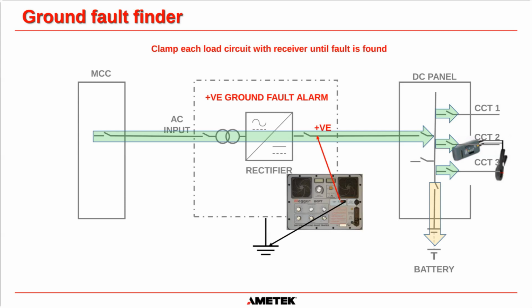I make it sound very easy using this equipment. I've used the system in the UK a lot, not this Mega one, but the one that I used to work. It does take practice. You do have to tune it. You have to read the instructions of the equipment and tune it before you start using it. But it's quite simple. It's in the instructions. It tells you how to tune it and set the amplitude of the voltage signal so you get the best signal on the receiver. Okay.